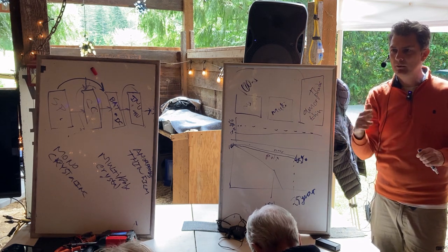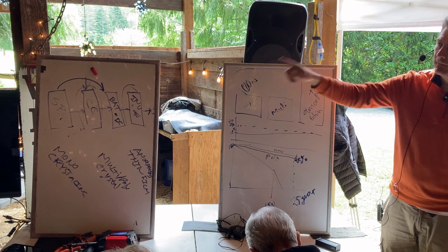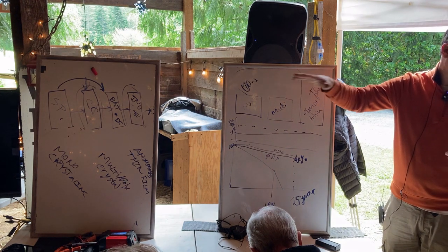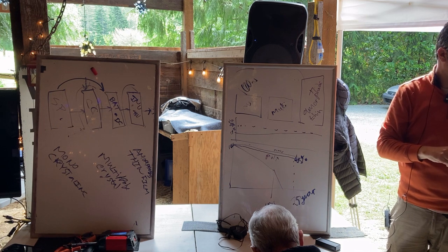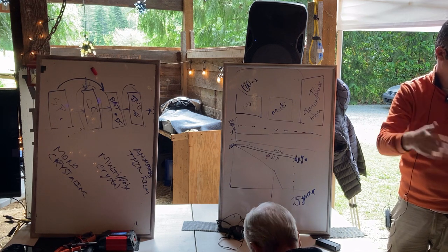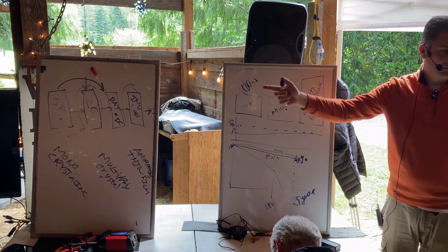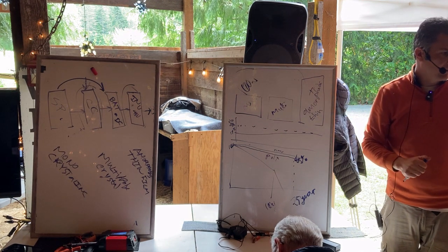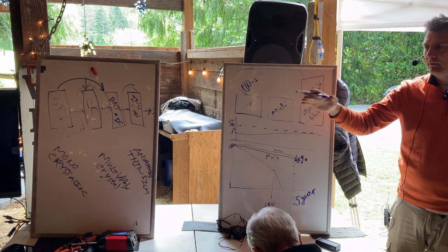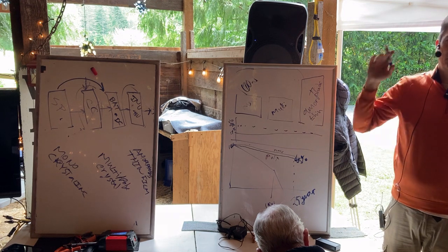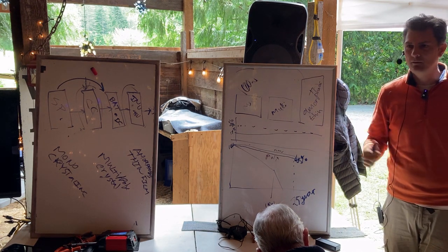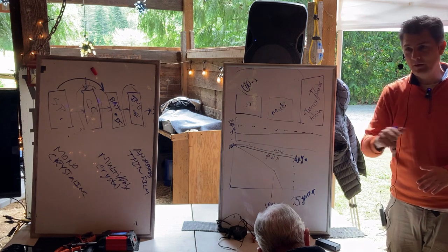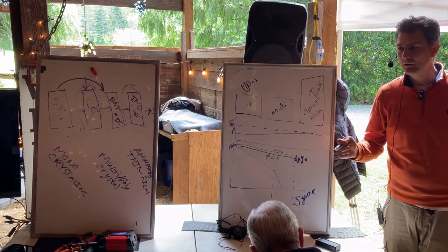So 5 kilowatt hours per day. So you'd need 5 of those panels to run a very light load in a house day in and day out. You have to keep in mind that has to be in full sun too and all that. But now that I've gone through it so many times, I design for 3 times what you need, at least 3 times. And then if you have winter concerns, you're 5 to 10 times what you're going to use in the summertime.